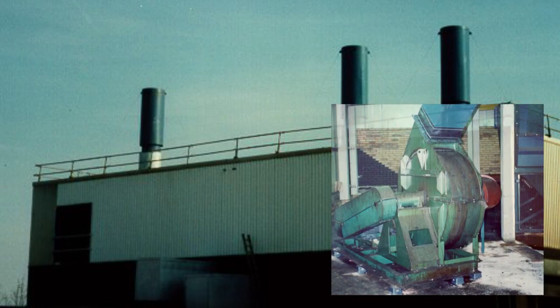Three new CAN recycling chopper fans created severe environmental and occupational noise problems. Instead of the proposed acoustic lagging, acoustic enclosures and silencers, Quiet Fan technology was used to reduce the noise by some 22dBA at around 10% of the cost of the proposed conventional measures.